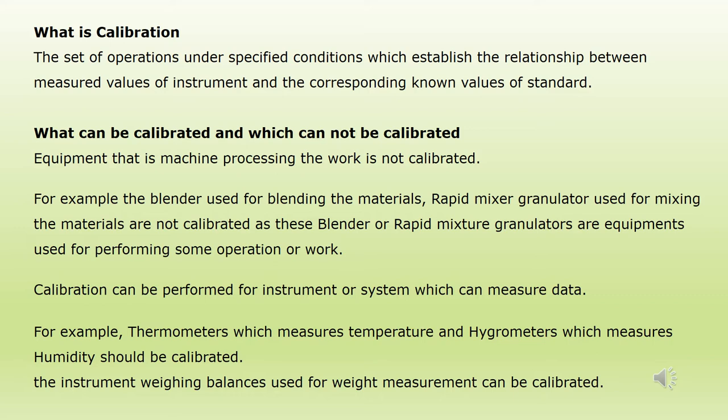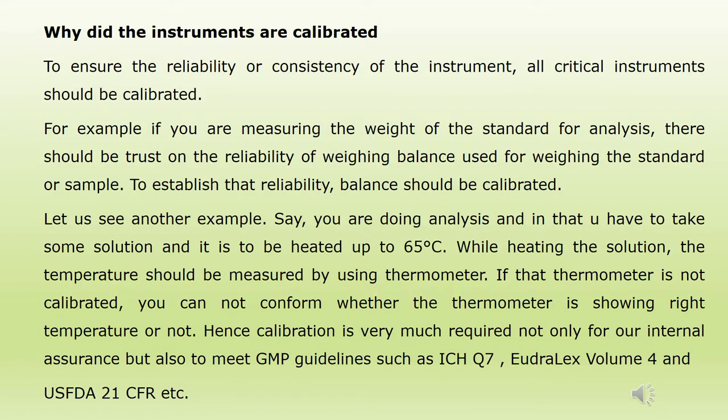A weighing balance used for weight measurement during manufacturing, packing, or analysis can be calibrated. Why are instruments calibrated? To ensure the reliability and consistency of the instrument. All critical instruments should be calibrated. For example, if you are measuring the weight of a standard for analysis, there should be trust in the reliability of the weighing balance used for weighing the standard or sample. To establish that reliability, the weighing balance should be calibrated.